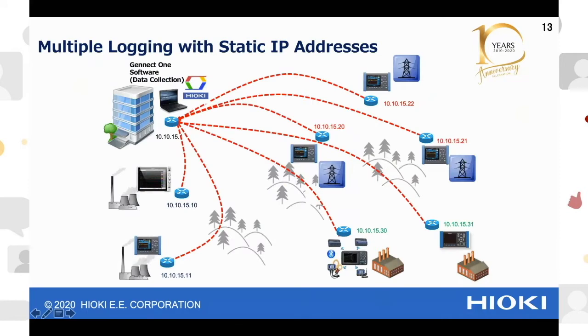So, if your customer has a need to monitor or log data from instruments that are far apart from each other, they are able to transmit data with the use of a static IP address. These are all static IP addresses. They are all fixed numbers which cannot be changed. However, the normal data SIM card that we have in our mobile phone or the tablet cannot be used because it is using a dynamic IP address. Dynamic means that it will change over time. Most telco companies are also using masking techniques to hide this dynamic IP address so that the router is unable to know the actual public IP address. So in short, the telco companies are forcing us to pay for a static SIM card for industrial usage, and this can be very, very expensive.